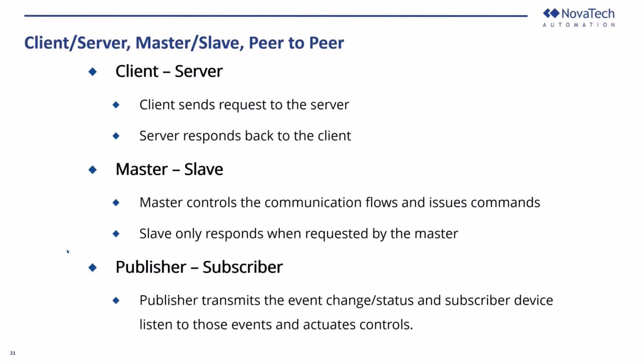And then we have peer-to-peer or publisher-subscriber. In this scenario, the publisher transmits the event change or status continuously, and the subscriber devices listen to those events and actuate based on whatever they need to do. One example of this protocol is 61850 GOOSE. It keeps on transmitting that data, and whoever is subscribing to it knows what to do. I like to explain this just like a radio. In your car, FM 99.9 is transmitting data. Whoever is subscribing to 99.9 gets that data and gets the music or whatever conversation is going on on the radio. That's in a nutshell the different architectures we talk about.